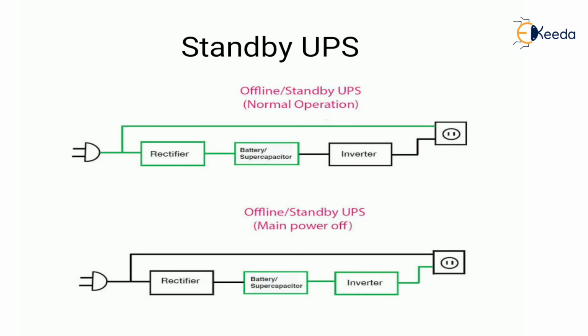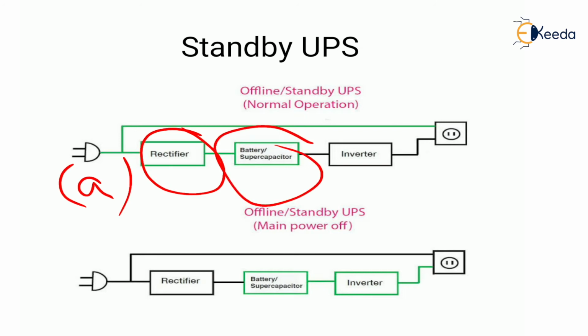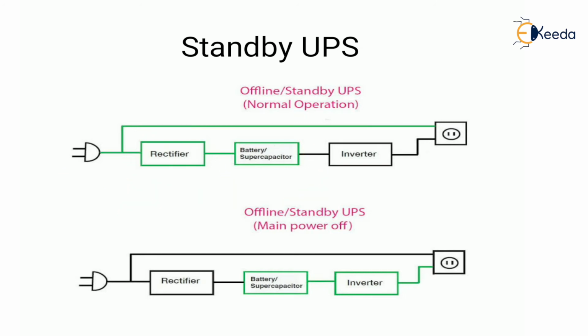So now let us see how it works. As you can see in diagram A, under normal operating conditions, the AC power from the utility passes through the UPS to the critical load, and a rectifier converts AC to DC to charge the battery. Now, when the main supply fails, as you can see in diagram B, the inverter is used to convert DC power from the battery to create AC power to support the load.